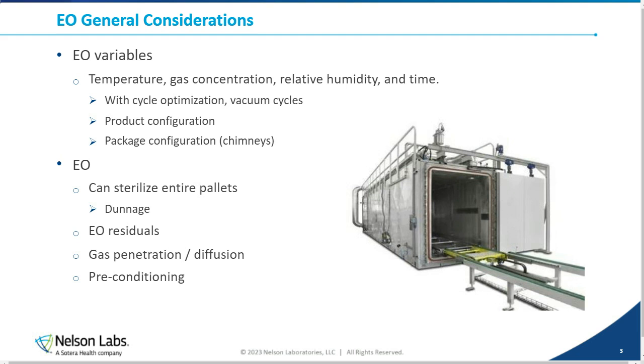Where you're really going to save if you do an EO optimization is probably on preconditioning. If we can save any time on preconditioning or on aeration, then we can do that. That's also a consideration with EO versus other sterilization modalities, in that there is a preconditioning step. Radiation, for example, has no preconditioning. That's not something to be concerned with. So those are the variables we want to consider when we talk about sterilization for EO.